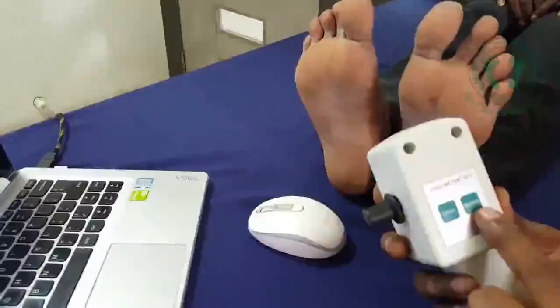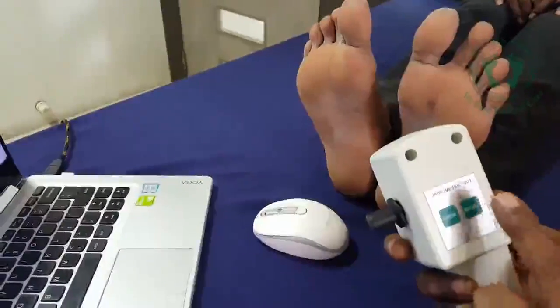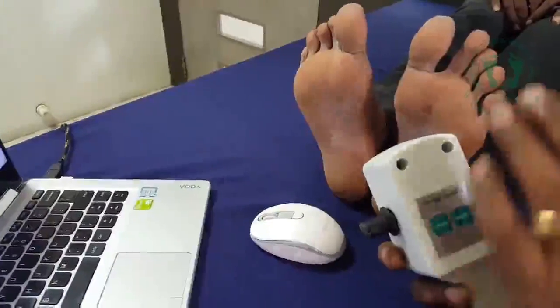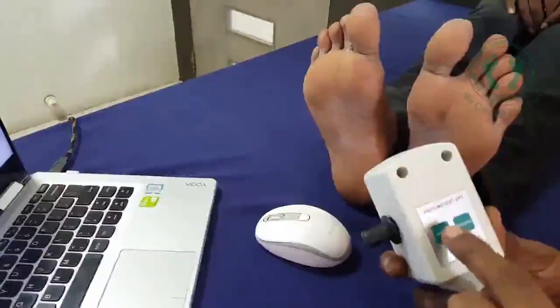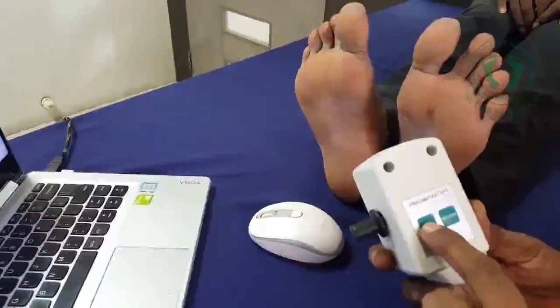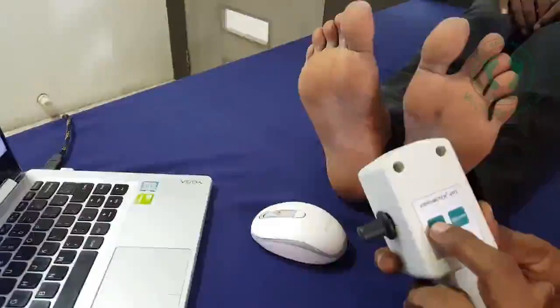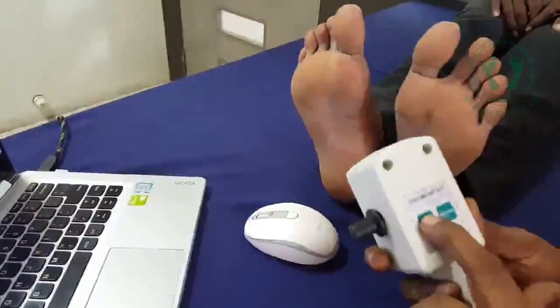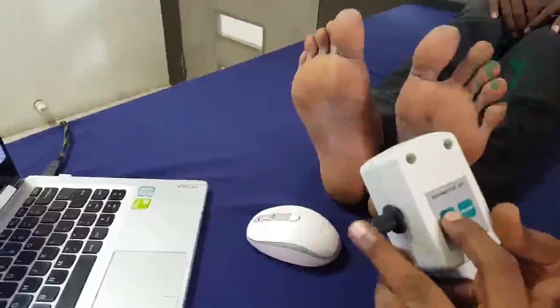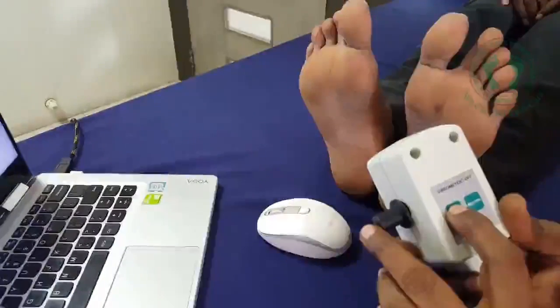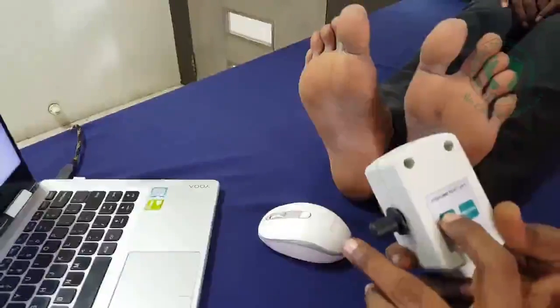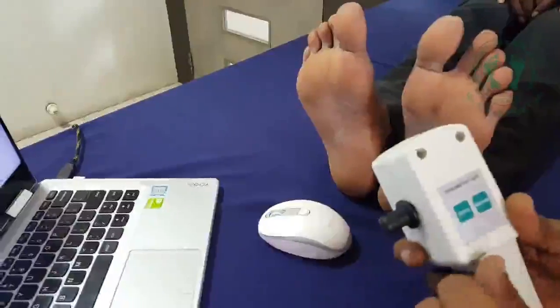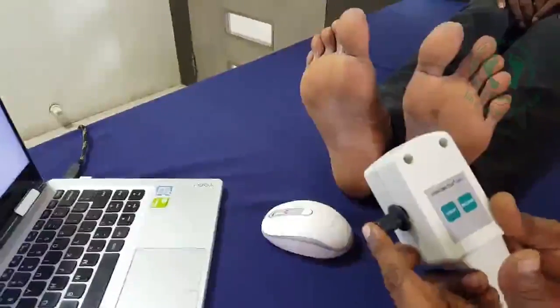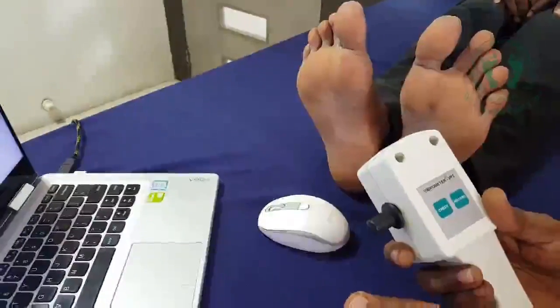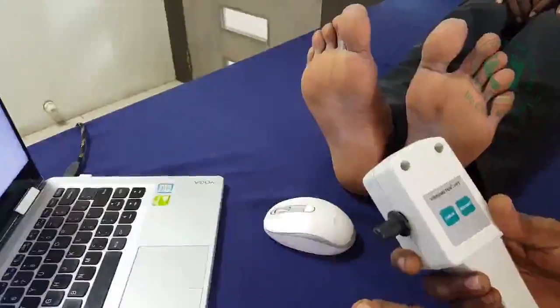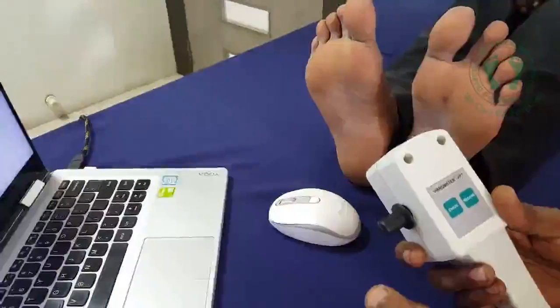One is check, one is record. Record is for transferring the data from the device to the computer. Check is actually to check whether the value the patient says is correct or wrong. When I press check, the vibration at the tip is stopped. So when I ask the patient, he should say he is not feeling it. The moment I release it, he will be getting the vibration. He should say I am getting the vibration. If that is so, then what he is perceiving is correct.